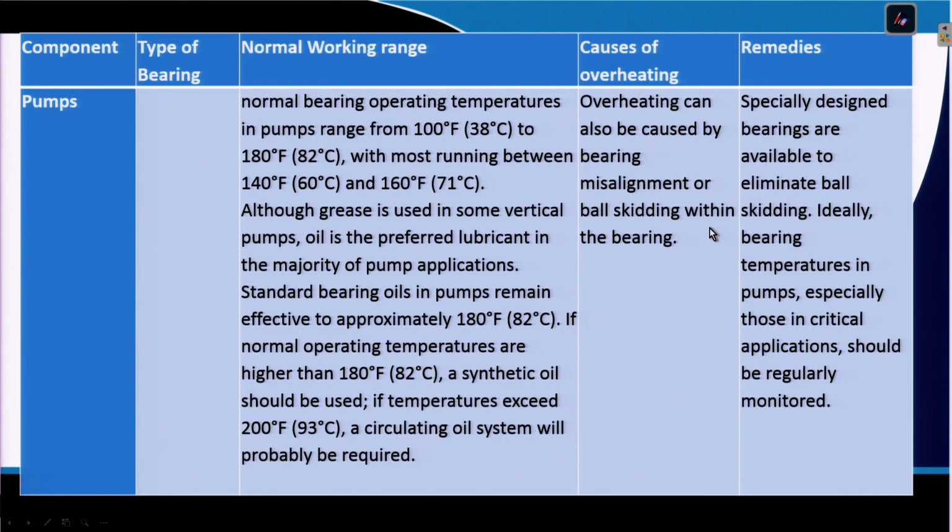Similarly, in pumps also they have different types of bearings and operating temperatures, and during normal operation they go to a higher temperature. Sometimes the pumps get a misalignment. If you get a misalignment of the shafts, it will give more friction and more noise, and as a result there can be more heat generation.